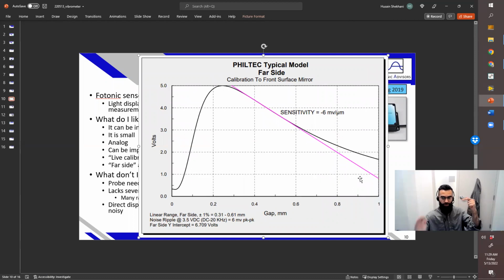If you took your sensor and moved it closer or farther—say from really far away—as you get close to the device, at 1 millimeter away you'll have a little less than 2 volts, and at this point you'll have 5 volts. As you get really close to the device, you'll have close to 0. So this is kind of a funky curve; we have to do something with that. You can't just use this full range, because it's not linear unless you programmed it that way and did some other functions on it.